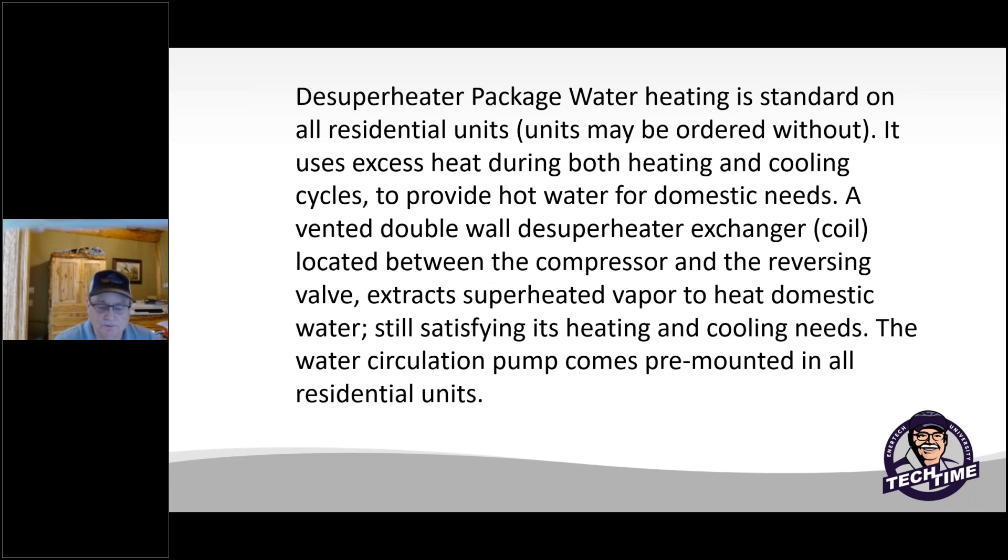It provides hot water for the domestic needs. We use a vented double wall desuperheater exchanger coil between the compressor and the reversing valve, and this extracts some of the superheated vapor to help heat the domestic hot water. The units still satisfy the heating and the cooling needs.